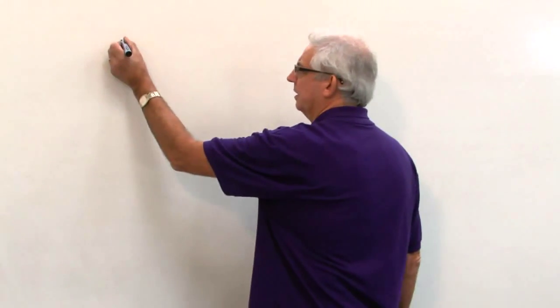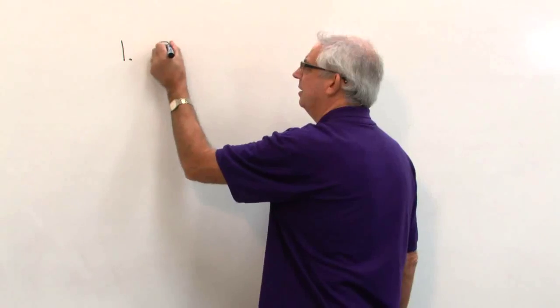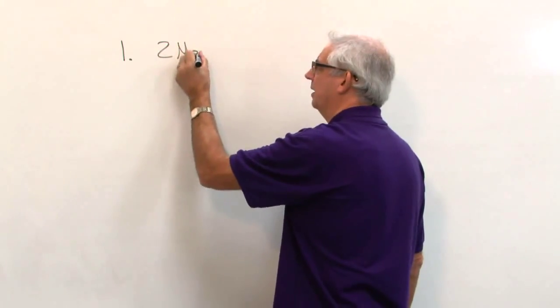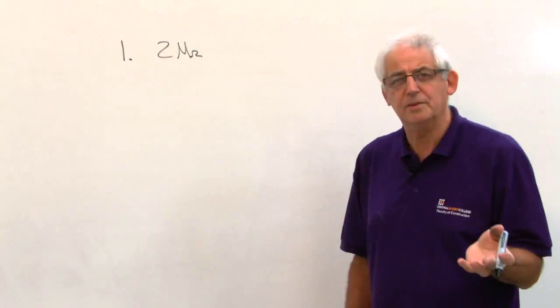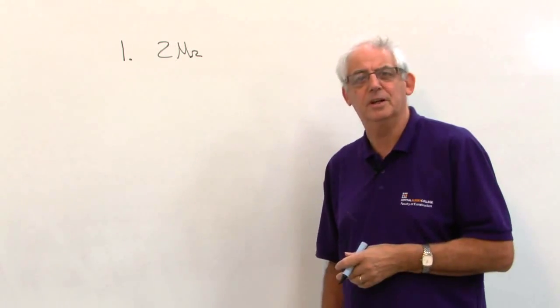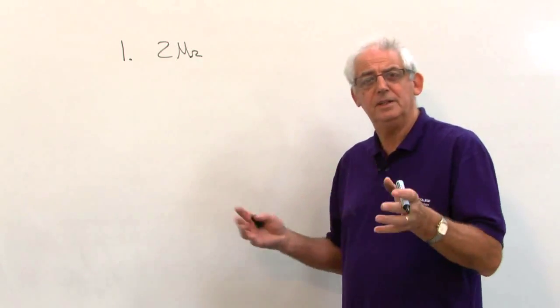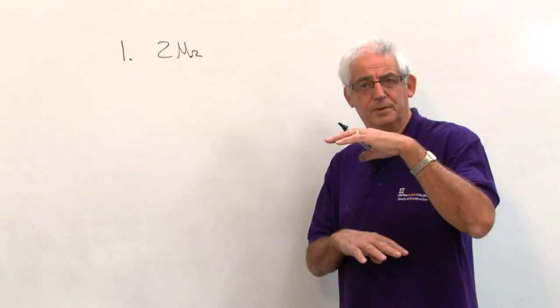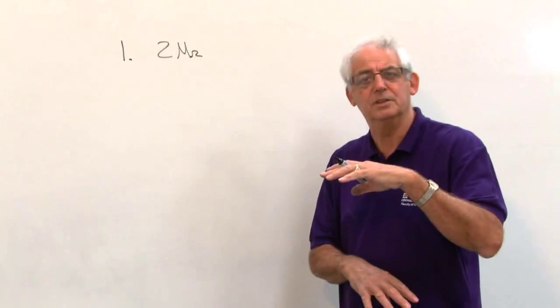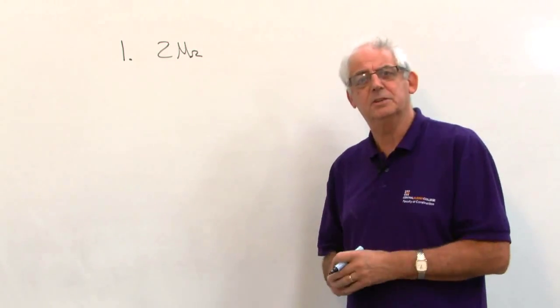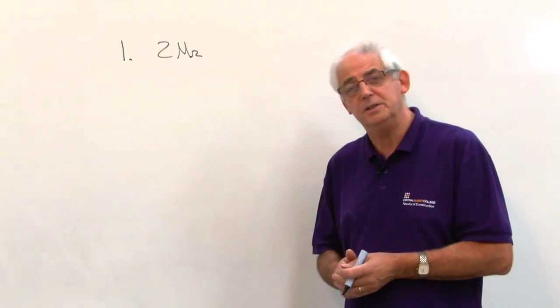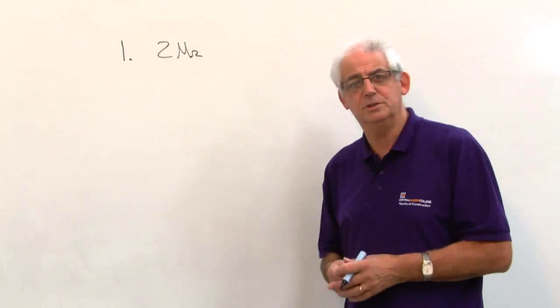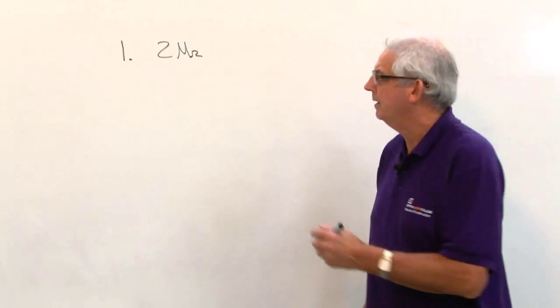If the first circuit is 2 megohms, we know it's very low, but this is purely a calculation to show you why we need to do a calculation of the whole of the installation when we've finished. Because some installations could have 10, 15, 20 circuits, which of course will reduce the resistance a lot.